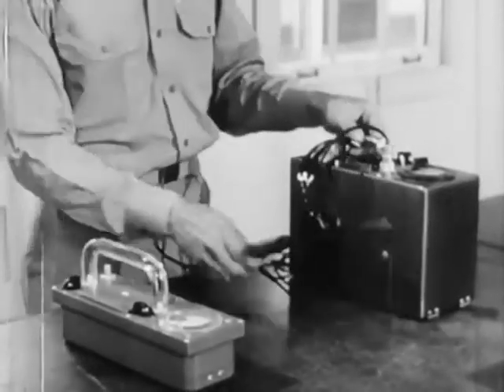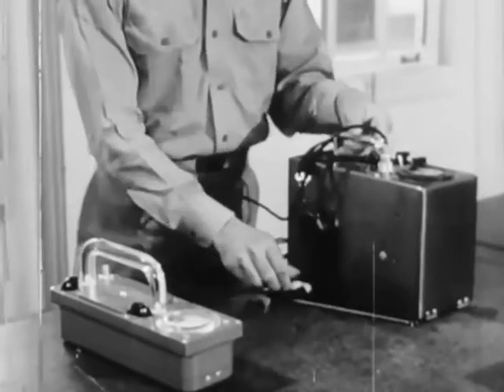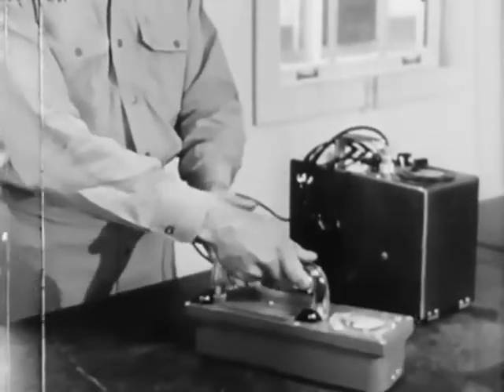The proportional counter, which has a greater charging voltage than an ion chamber, will count alpha particles in the presence of a strong beta-gamma background.